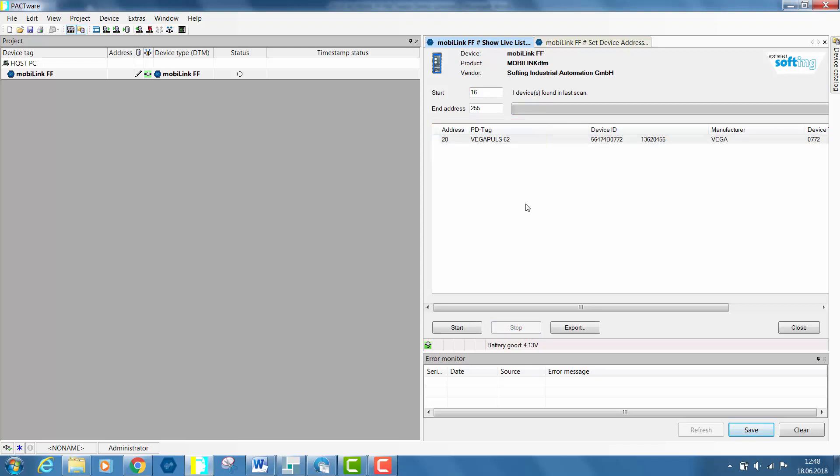In the second use case, we will add a second FF device. One level sensor from VEGA with node address 20 in our topology. In this case, both devices are configured with the node address 20. This typical use case can happen during the commissioning of a new field device. The same node address cannot be used on the same FF segment by two different field devices.